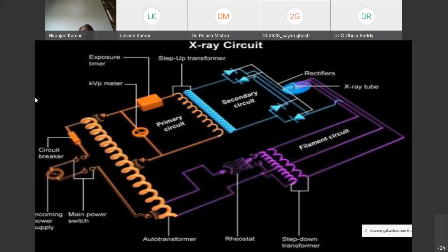so this is how the first X-ray generator came. When I won't say first, it means a little bit of advancement. First was just a transformer, because in an X-ray tube, if you understood, only one direction current comes. So even if you give AC across the tube, only one direction current will go. But this is the second generation. So it is just a transformer and the rectification. Okay, so you actually have a high voltage transformer, and you just rectify and give across the X-ray tube.